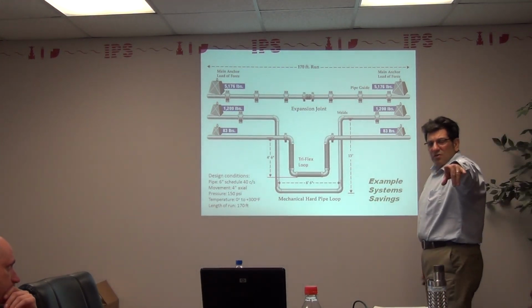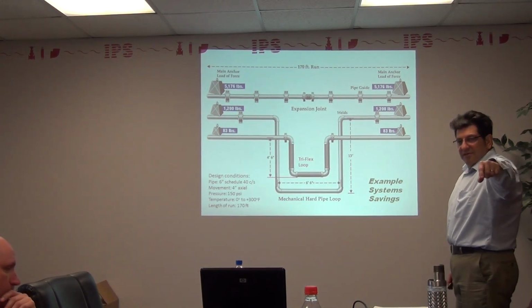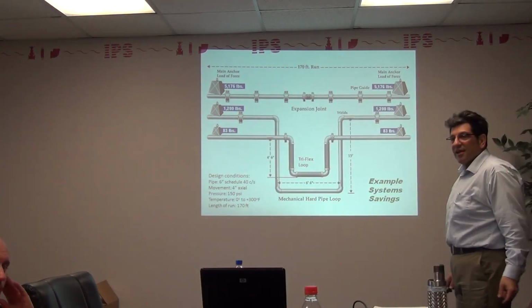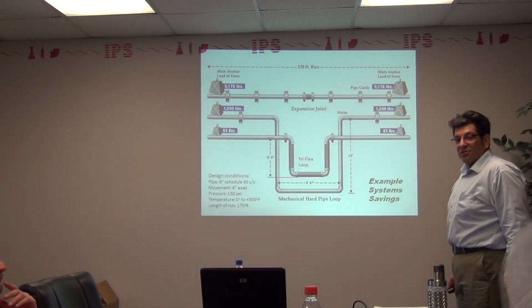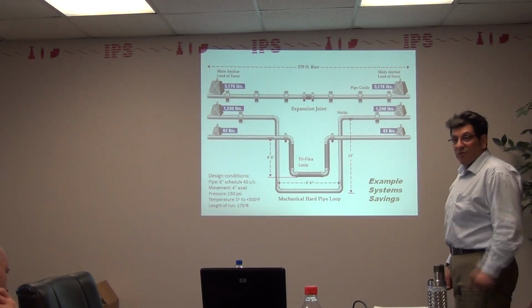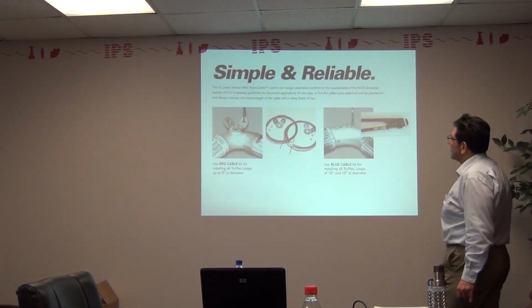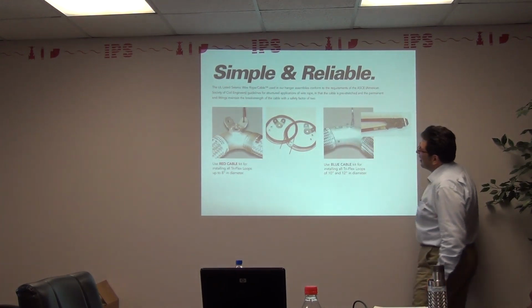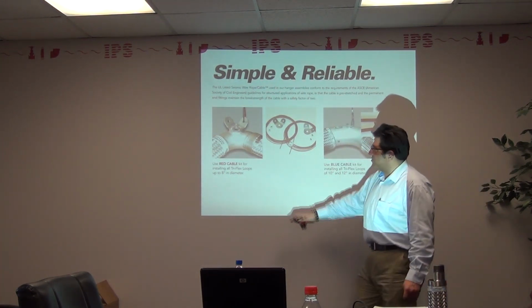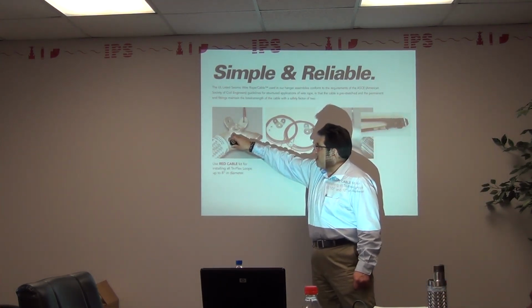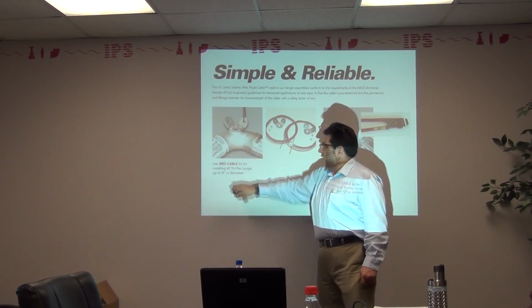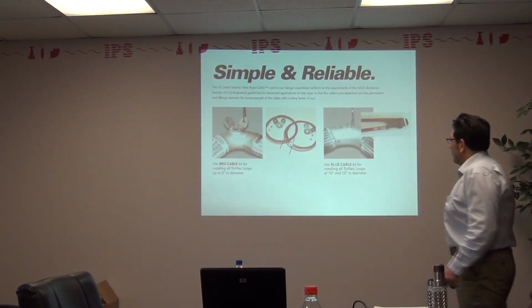You hang it - can you hold up that bag right in the middle of there? That's nice support right there on the table. It's UL certified break strength cable that they would crimp right onto the device. There's a good detail of that, right onto these URC clips, universal restraint clips, and you can see they're load rated. This has been welded on by an ASME Section 9 welder.